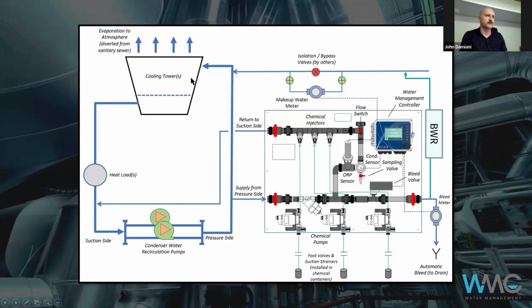The challenge with the fluid coolers is they can be hard to treat, because you don't have a recirculating condenser line that you can just tie into. So sometimes you have to come off the discharge side of the spray pump, for example. The cooling tower manufacturer doesn't always like that, because now you're taking flow from the cooling, right? So you might have to install a line that comes off the basin and returns back to the basin. In that case, you don't have flow, so you need to install a pump, like a booster pump, to be able to feed into the treatment panel. But as far as the treatment, it would look basically the same as this. You need to do all the same things. So I hope that answers your question.